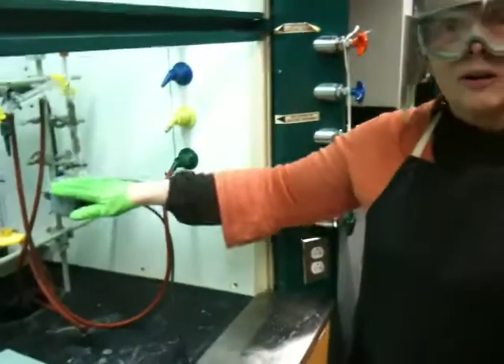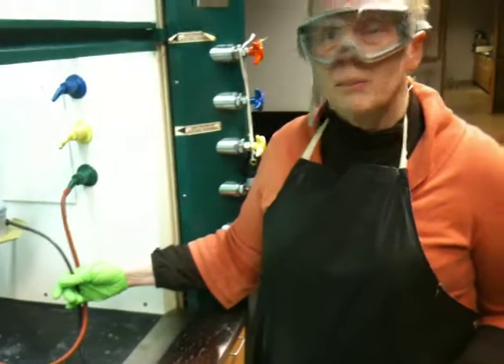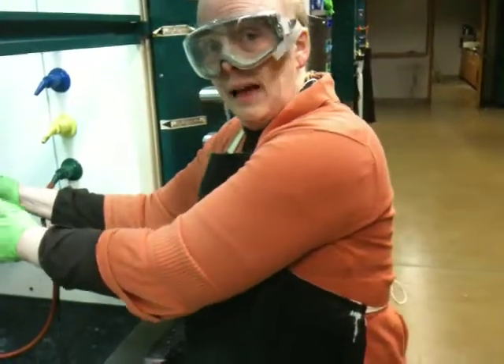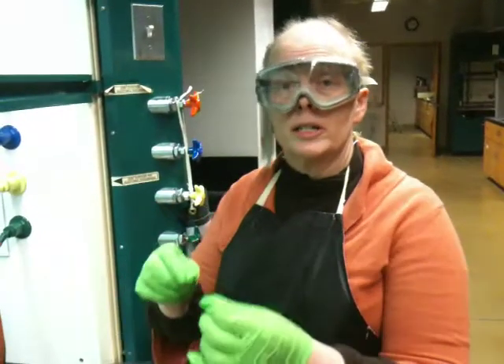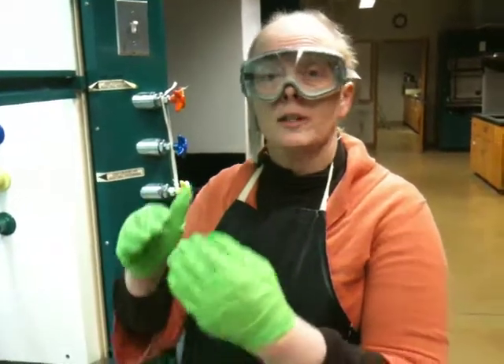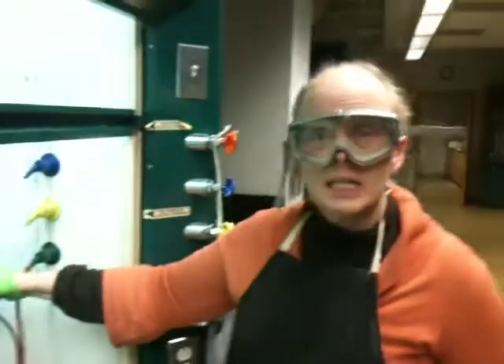Check out your heater. These heaters take a beating, unfortunately. When you put the heater away, put it away holding the top piece, as long as it's cooled down. However, do not whip the heater around by its cord. When you do that, the cord separates. If the cord separates, you have a greater chance of exposing the wire or having the wire separate. If the wire separates, you get an arc, and then you get sparks. So make sure your apparatus is in good condition, there are no cracks in it, and it's sealed up. If it's not, just turn it in — we will get it fixed or get you a new one.